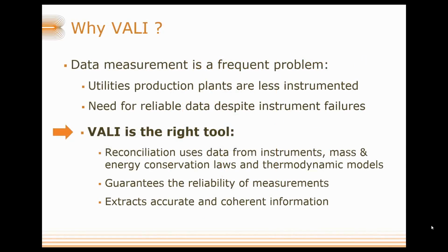Why has Vali been chosen as the reconciliation tool? Utility systems typically do not have a very high level of instrumentation, but at the same time, this data is very crucial for the quality of optimization tools or any other process analysis tool. Vali is the right tool for this because it takes redundancy from the process, reconciles data, corrects them and performs mass and energy balancing by using thermodynamic models.